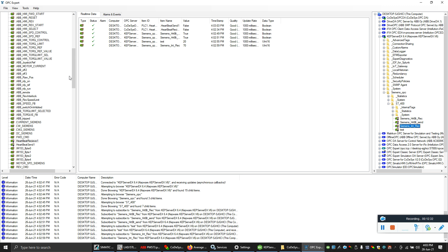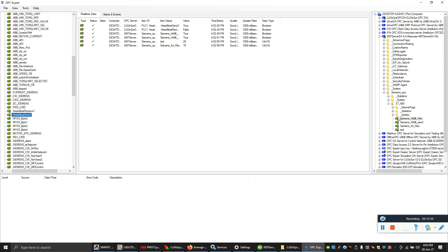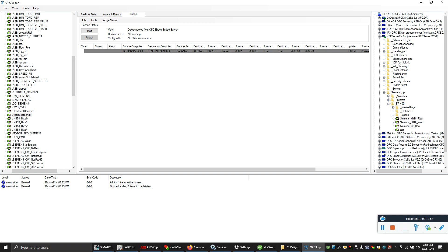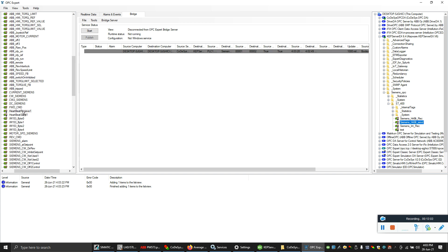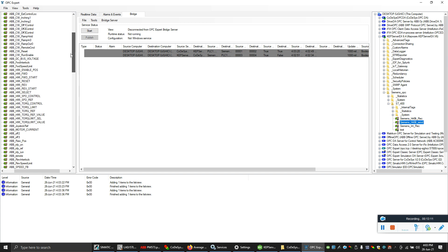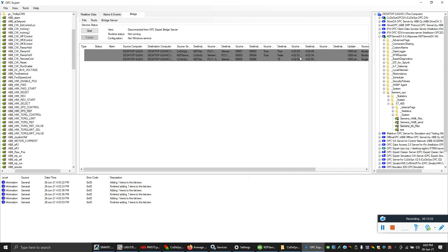Now we need to send the heartbeat to the Siemens receive heartbeat tag. I'm going to send from the ABB heartbeat send to the Siemens heartbeat receive — it's so easy, just drag and drop. Now I also need to receive the heartbeat back to ABB, so drag from the Siemens heartbeat send and drop it onto the ABB heartbeat receive. Let's also define the integer value link — drag and drop that across. A warning appears, just click OK. Our bridge is now done — click Start to start the service.